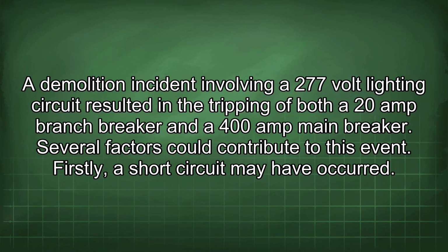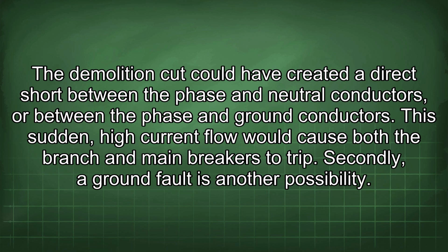A demolition incident involving a 277-volt lighting circuit resulted in the tripping of both a 20-amp branch breaker and a 400-amp main breaker. Several factors could contribute to this event. Firstly, a short circuit may have occurred. The demolition cut could have created a direct short between the phase and neutral conductors, or between the phase and ground conductors. This sudden high current flow would cause both the branch and main breakers to trip.